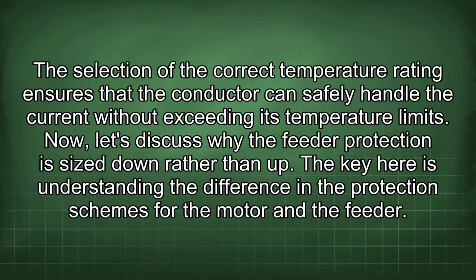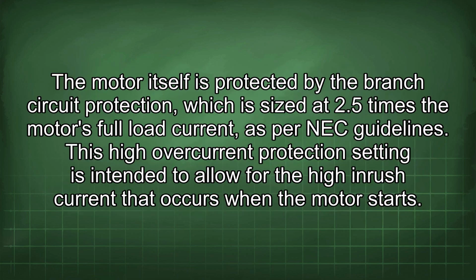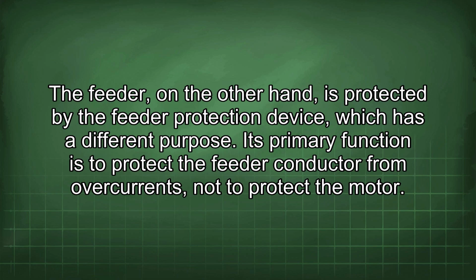The key here is understanding the difference in the protection schemes for the motor and the feeder. The motor itself is protected by the branch circuit protection, which is sized at 2.5 times the motor's full load current, as per NEC guidelines. This high overcurrent protection setting is intended to allow for the high inrush current that occurs when the motor starts. The feeder, on the other hand, is protected by the feeder protection device, which has a different purpose. Its primary function is to protect the feeder conductor from overcurrents, not to protect the motor.